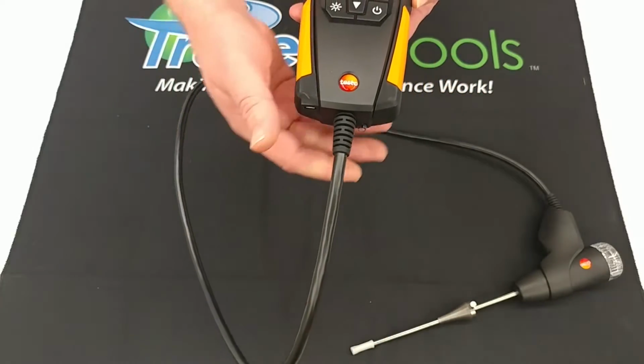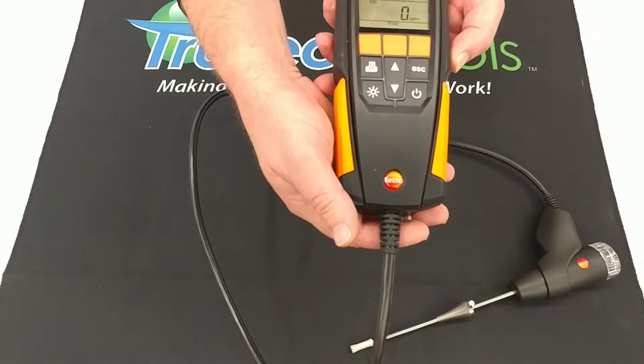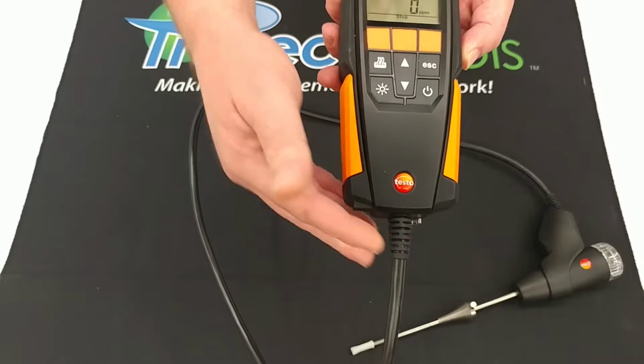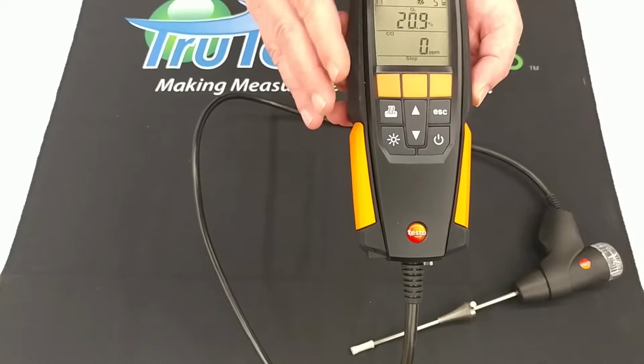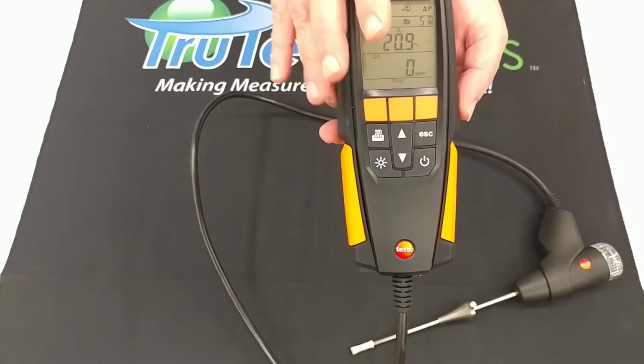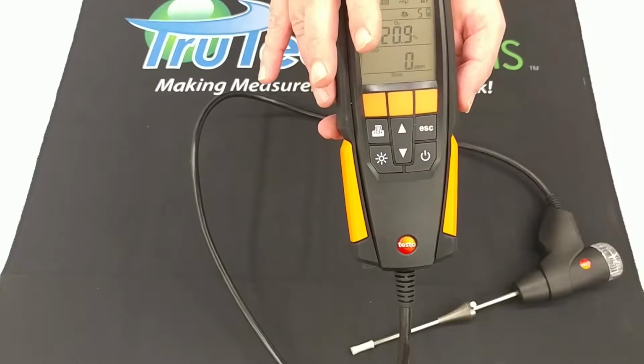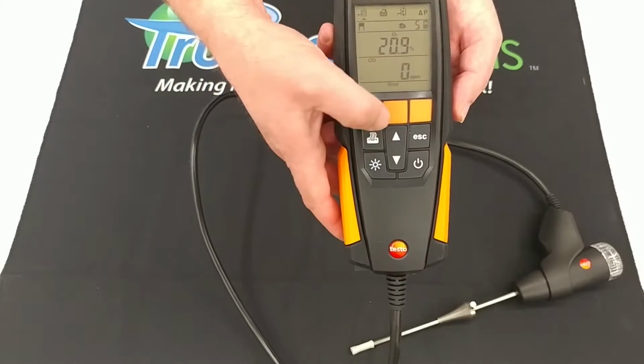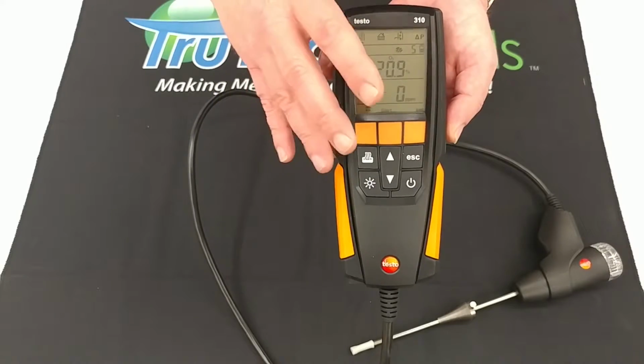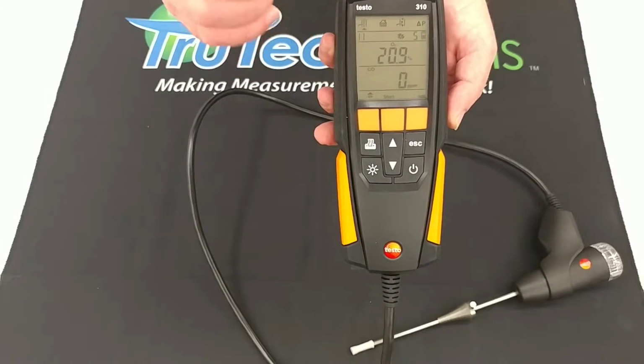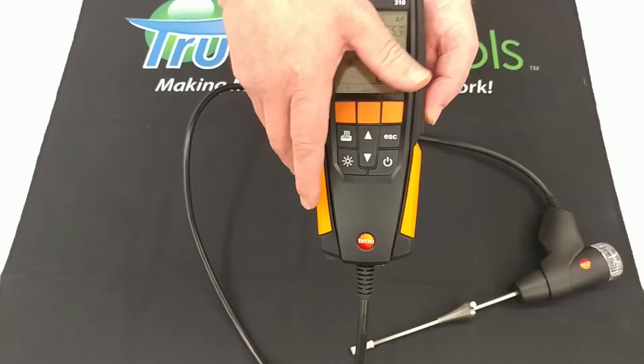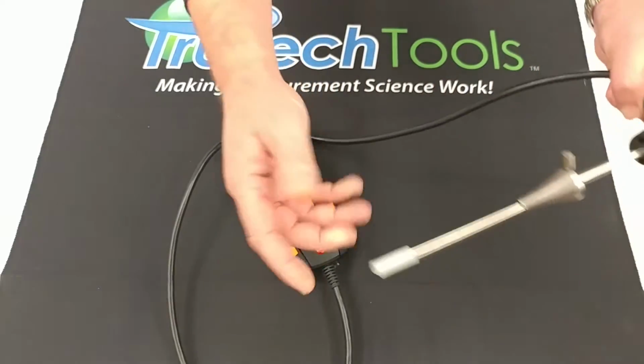We want to notice here that the probe assembly is permanently attached to the Testo 310. It cannot be removed nor replaced without sending it to Testo. The sensors in this piece and the calibration can only be done by Testo. It does carry a 2-year warranty on the product itself, including the sensors, with the exception of the battery and the thermocouple in the temperature and the probe assembly here.